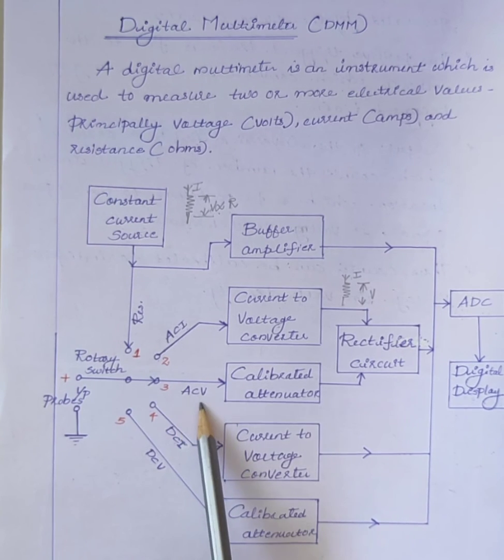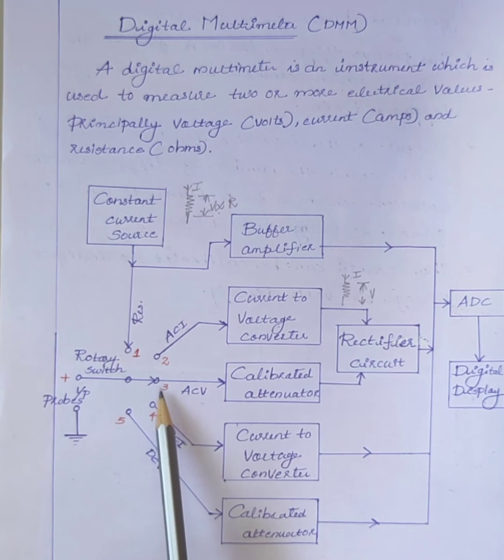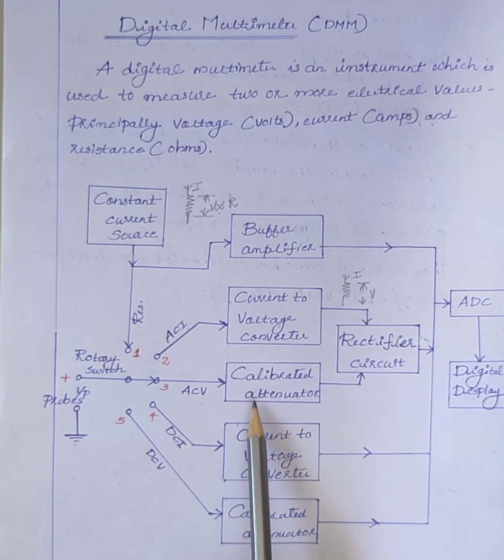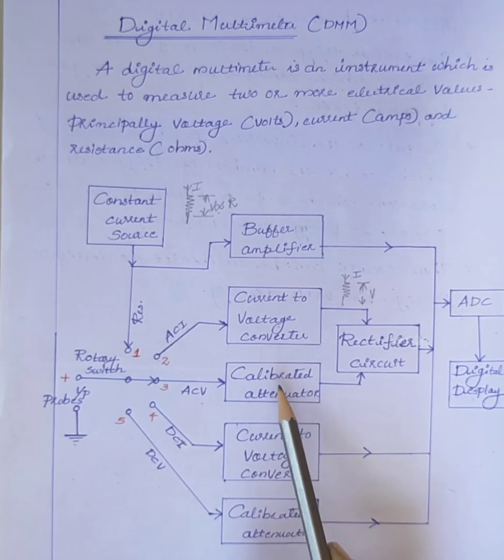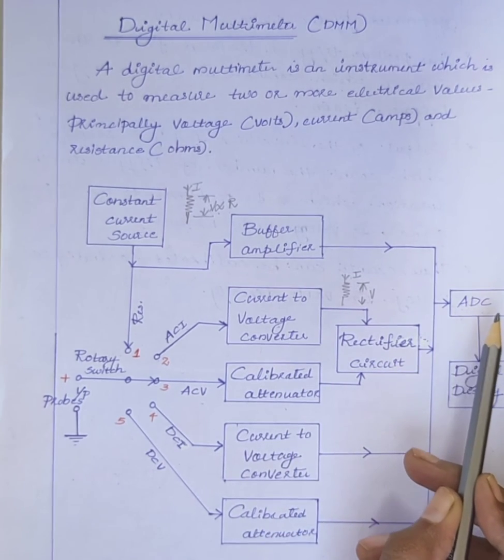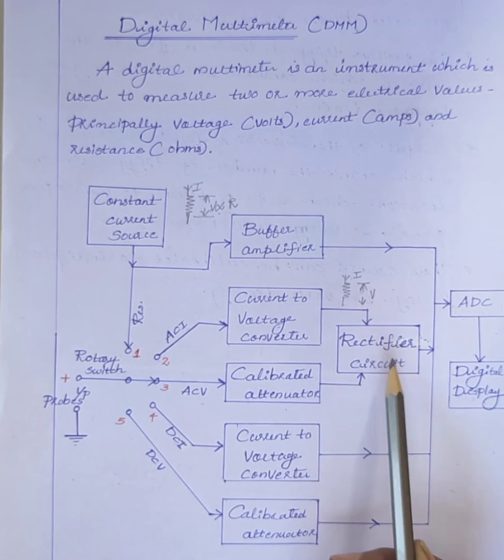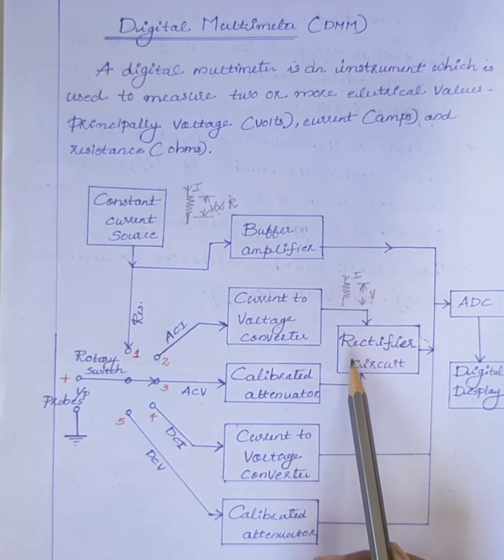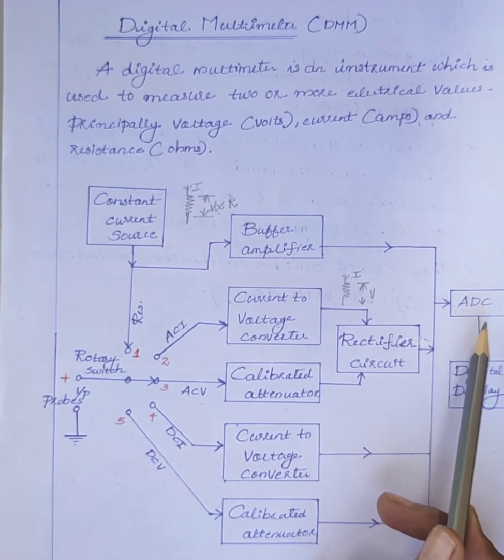Next is the measurement of AC voltage. For the measurement of AC voltage, the rotary switch is connected to terminal 3, and it is given to a calibrated attenuator. The function of the attenuator is to step down the voltage to a value suitable for the analog to digital converter. Then the output of the attenuator is given to the rectifier circuit, and the rectifier converts AC voltage to DC voltage and gives it to the analog to digital converter.